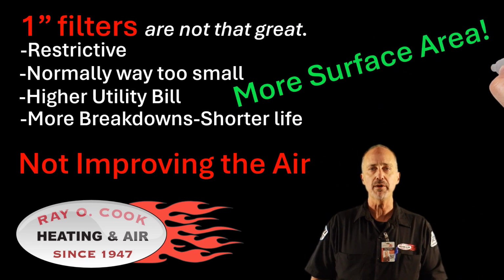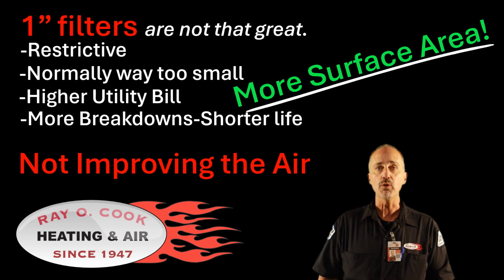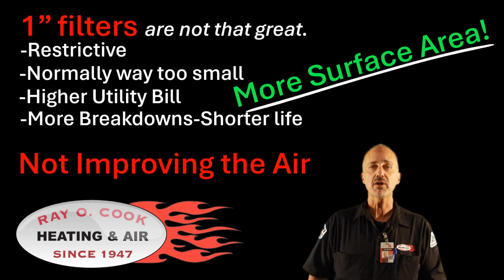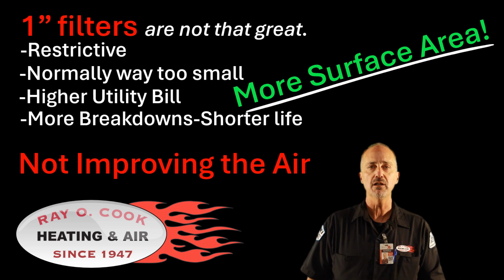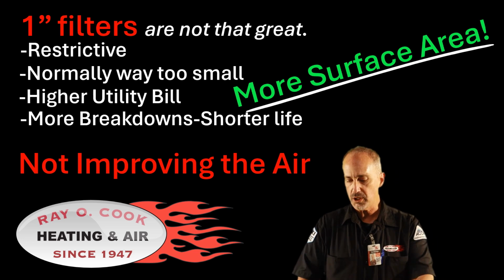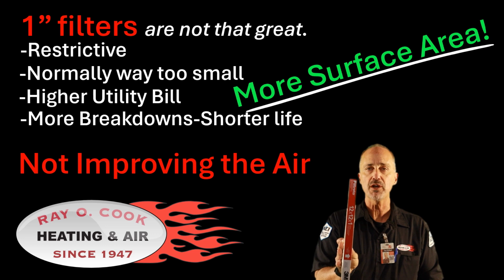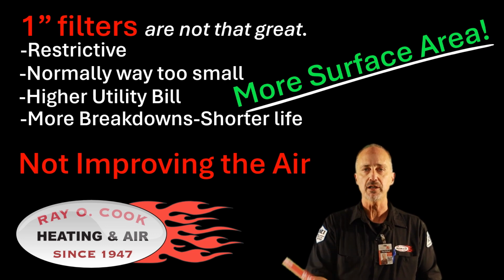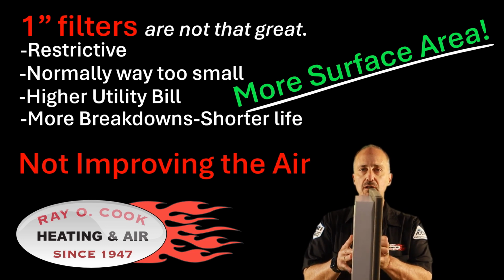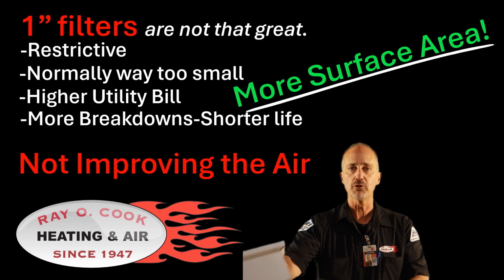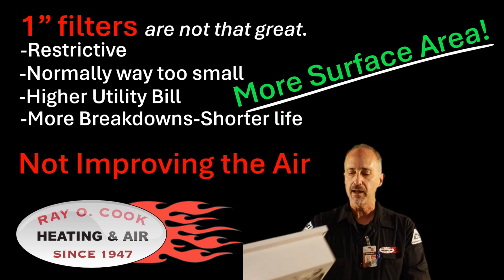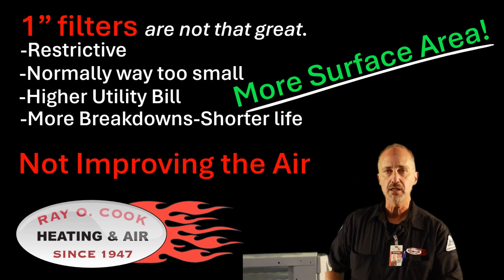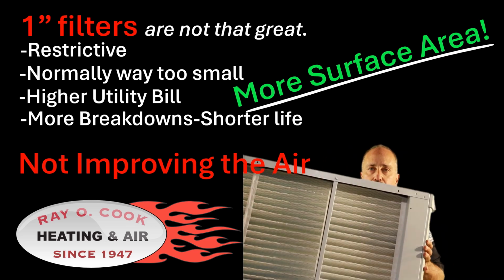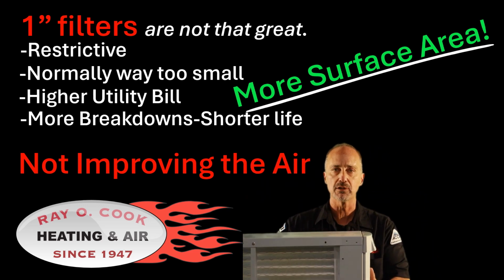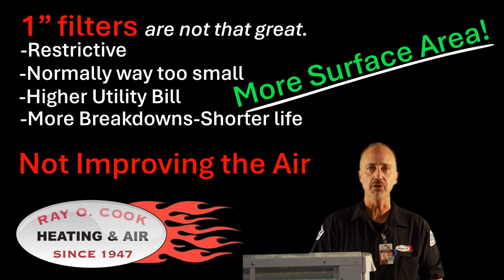Third, if you desire better air filtration, increased surface area, a bigger filter, will win the day every time. When we can spread the filter restriction over a large area, we lower the restriction. 1-inch filters simply cannot spread the restriction over a big enough area. 3-inch filters will help a lot. 4-inch filters are even better. And the best scenario for you is a 4-inch filter mounted in a housing at your equipment, and that offers the best of all solutions.